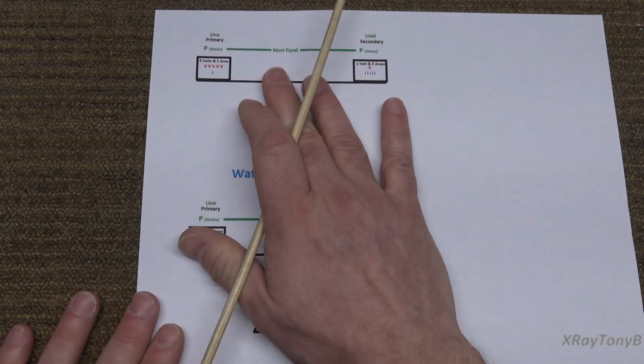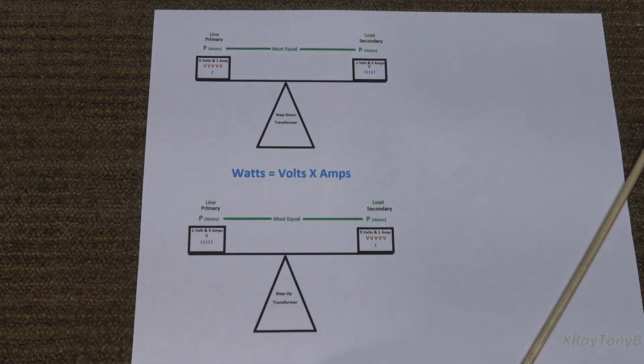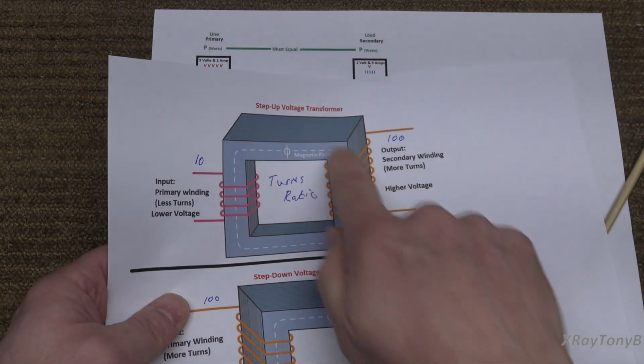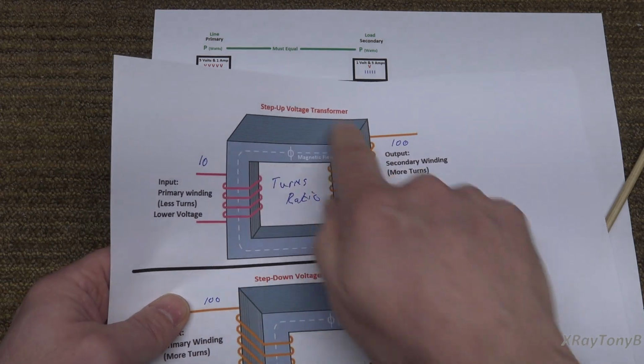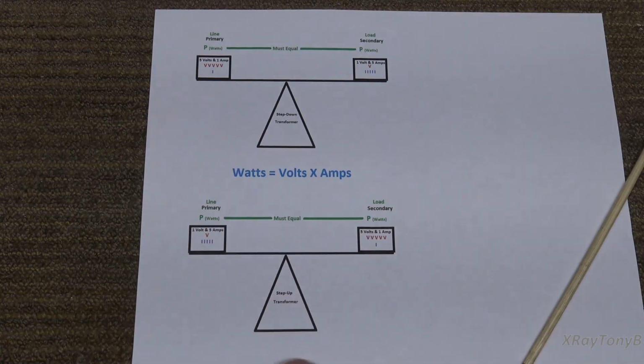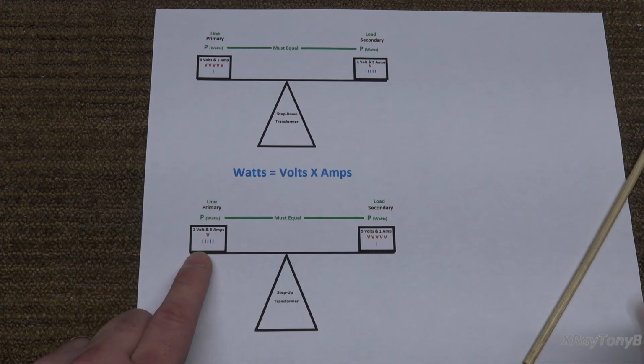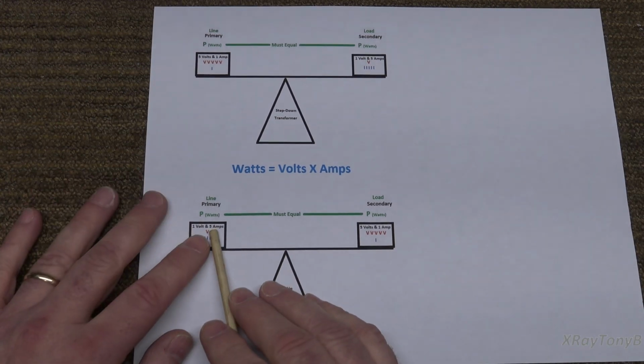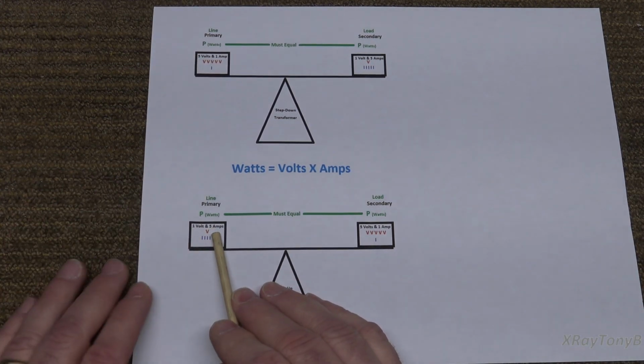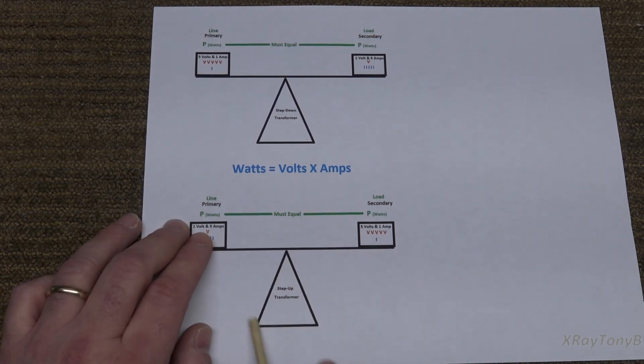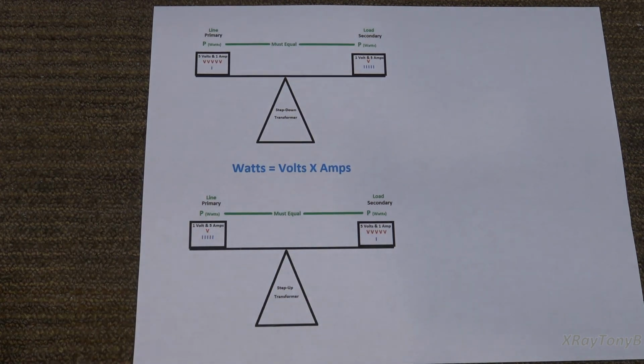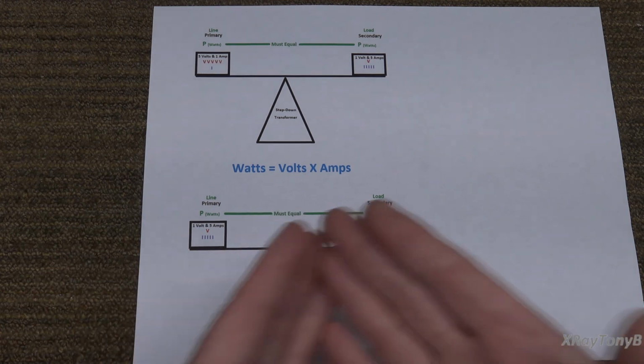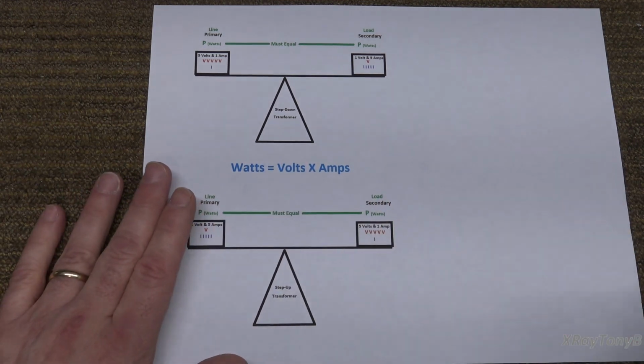Now, this is an ideal situation. In the real world, as we discussed, we lose a little energy through the core, so really we need a bit more than 5 amps — a little higher, not much, to compensate for the loss. This is all basic transformer stuff. So what I'm saying is you need a transformer that matches the load it's going to drive.